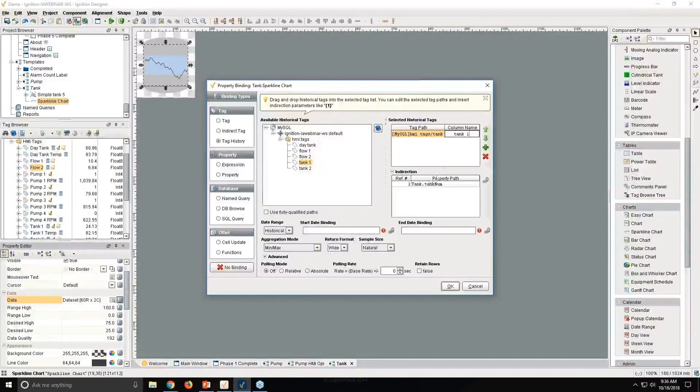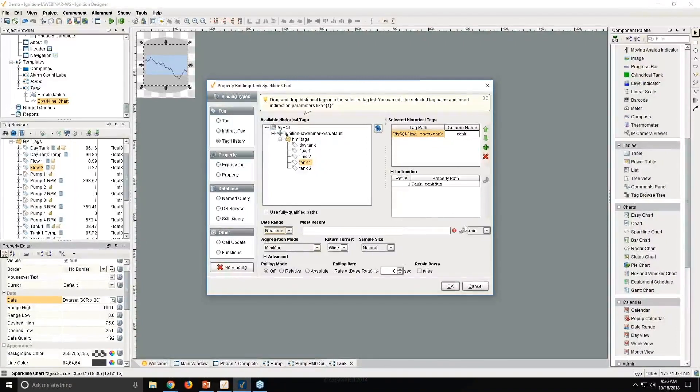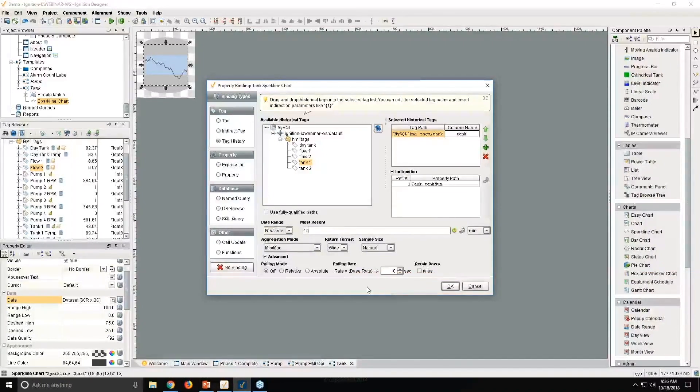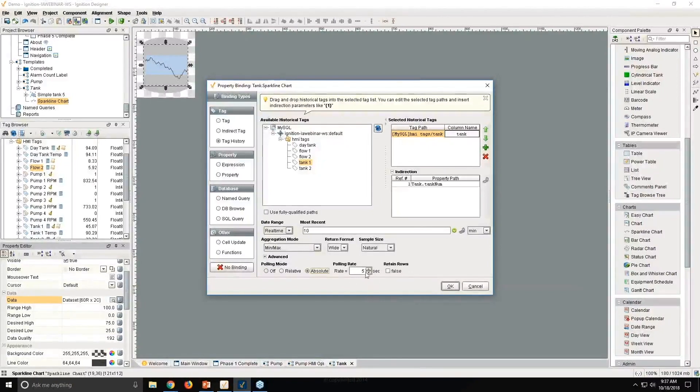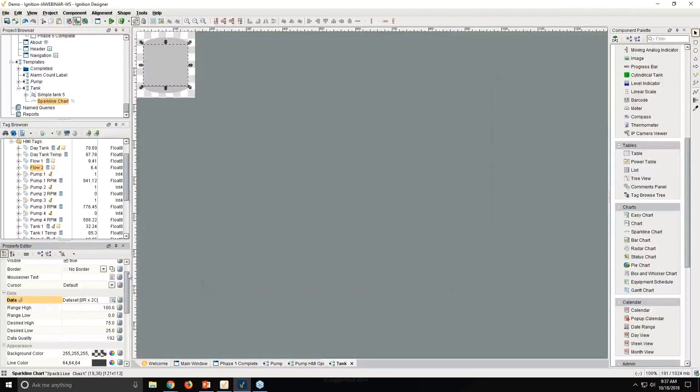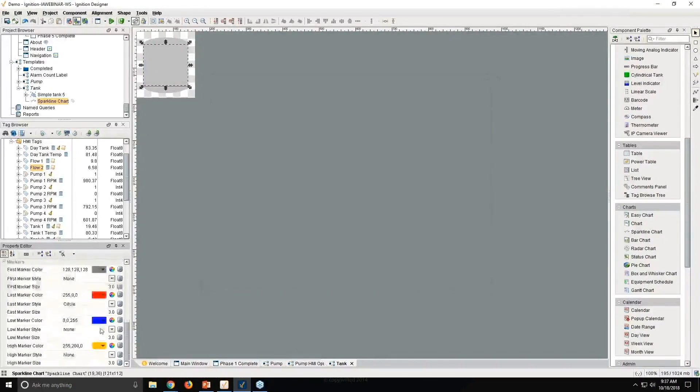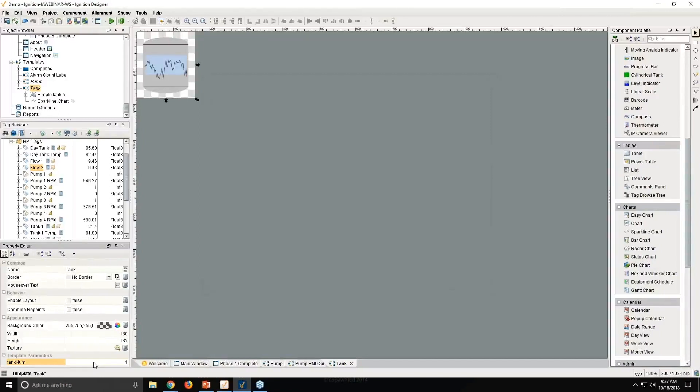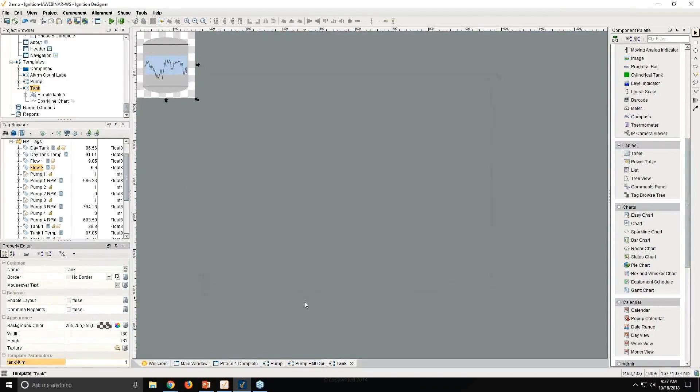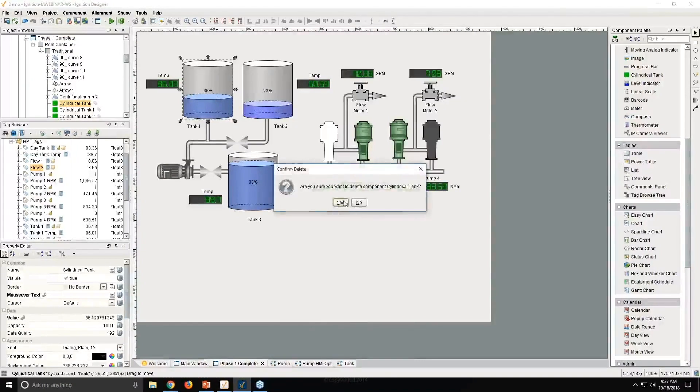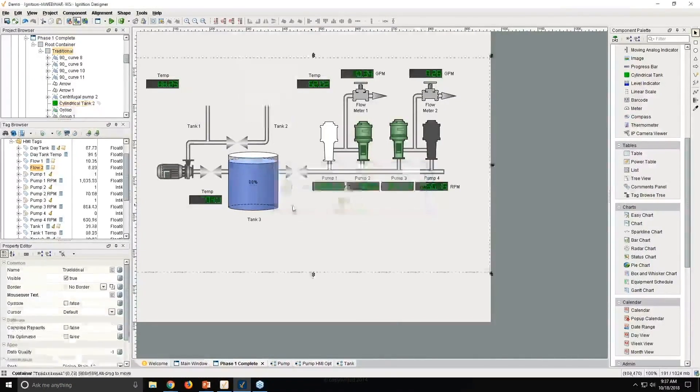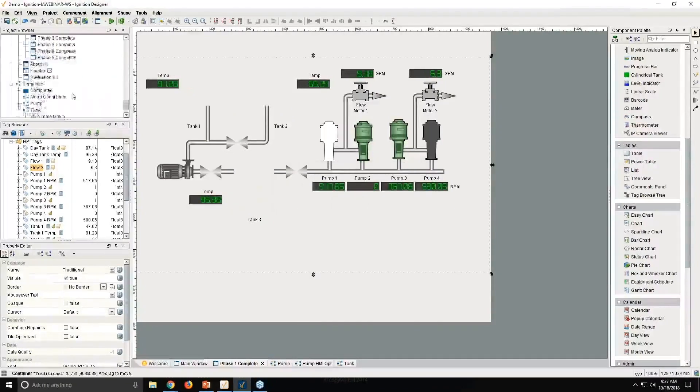We're going to have our time range just be the last 10 minutes worth of data. I could set a poll rate that I just want this to grab the latest data every five seconds, 30 seconds, whatever makes sense. I'm going to go ahead and say OK. You see it's not there yet because I haven't given tank num property yet. But if I give it one, for example, I can see the values coming in from tank one. So with that, our tank template is now complete. Let's go ahead and go back to our screen here. We can replace some of these tanks that we have here with our new tanks.